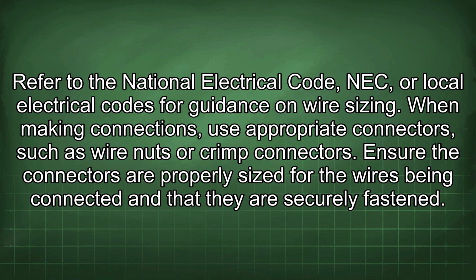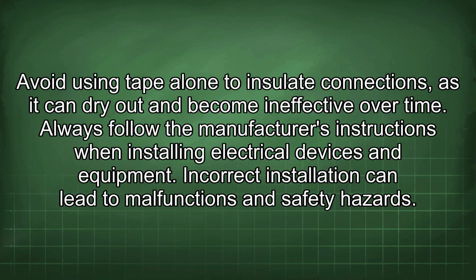When making connections, use appropriate connectors, such as wire nuts or crimp connectors. Ensure the connectors are properly sized for the wires being connected and that they are securely fastened. Avoid using tape alone to insulate connections, as it can dry out and become ineffective over time. Always follow the manufacturer's instructions when installing electrical devices and equipment. Incorrect installation can lead to malfunctions and safety hazards.